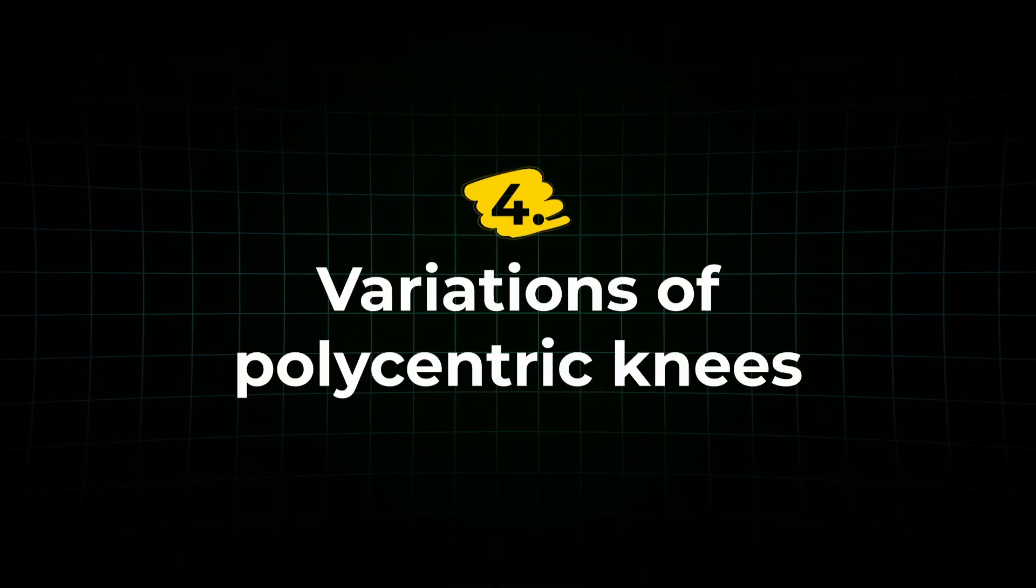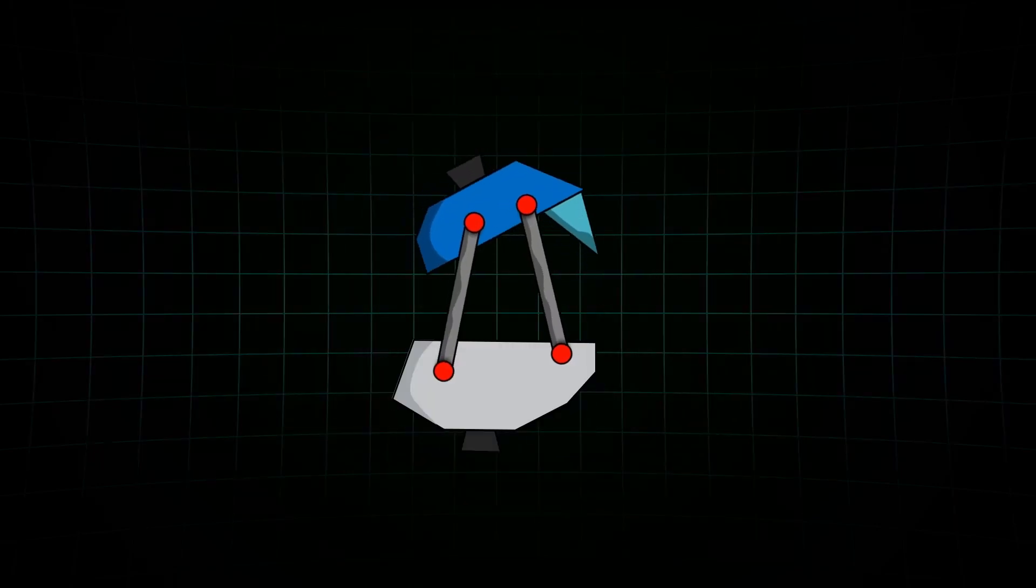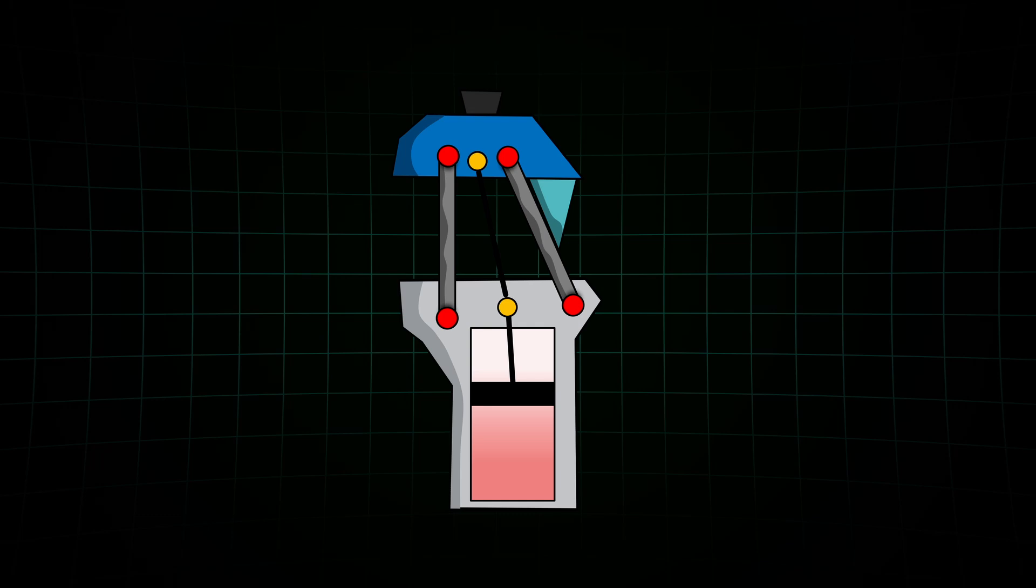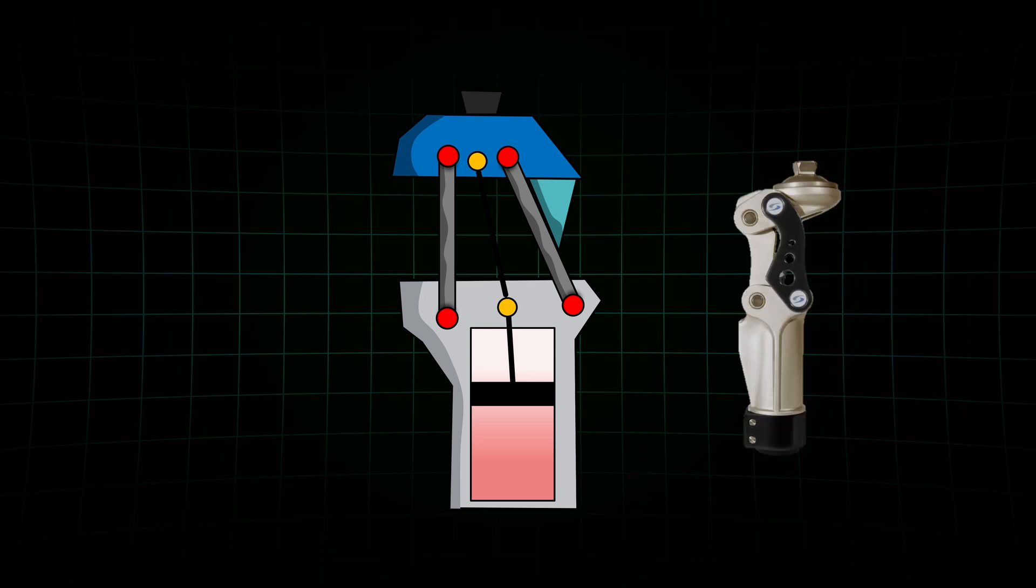Now we have one big problem. We can't adjust the flexion and extension resistance at all. Until now. Some polycentric knees add extra components, like air-filled cylinders. These cylinders compress air to create adjustable resistance during flexion and extension. The more you compress the air, the more resistance you get. The resistance can be tuned with valves, giving prosthetists control over how the knee behaves.